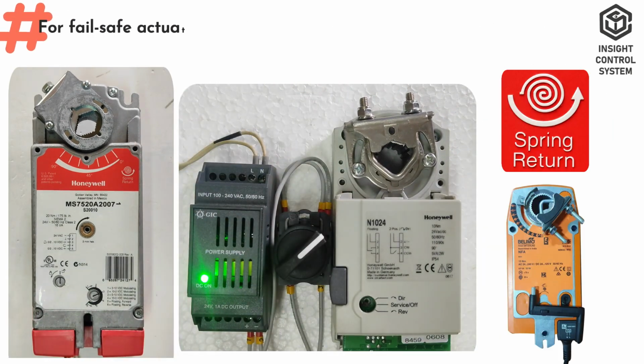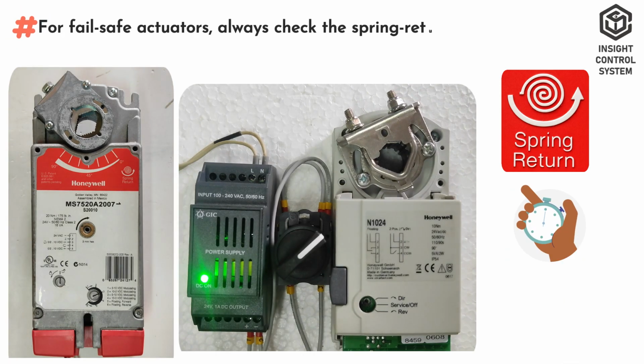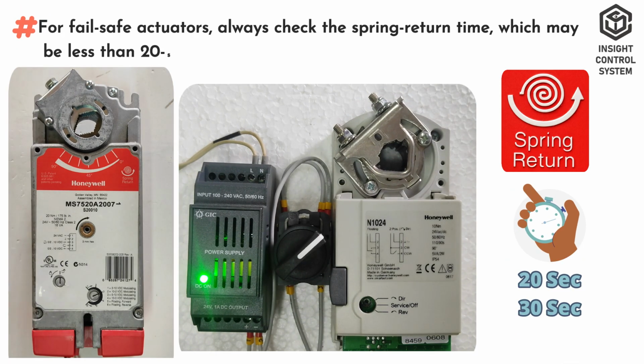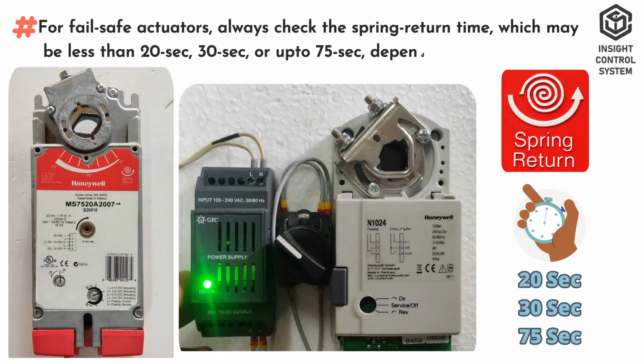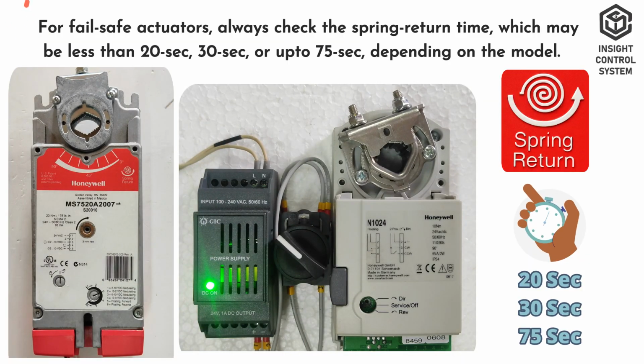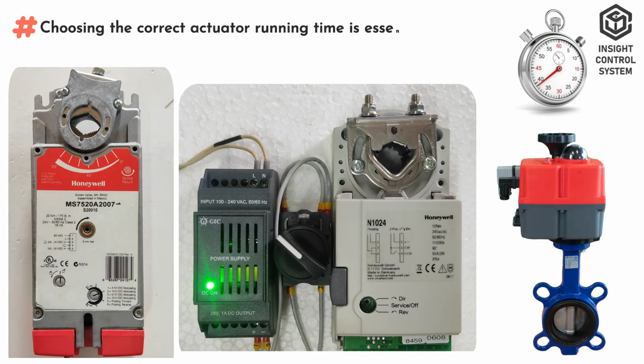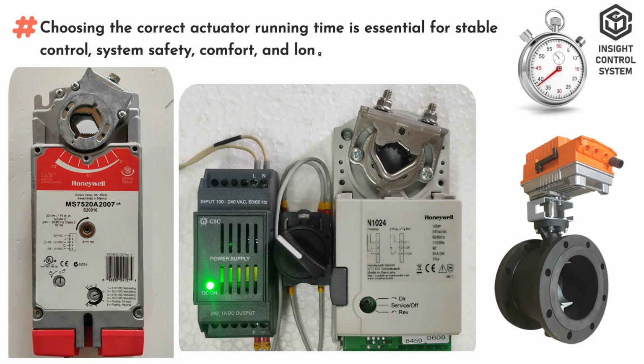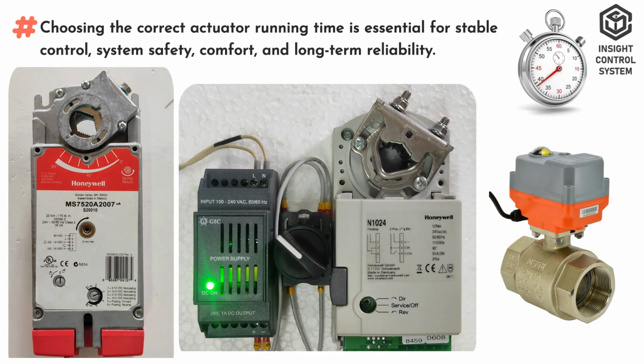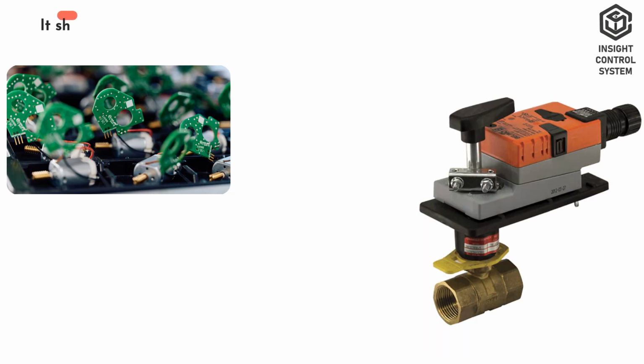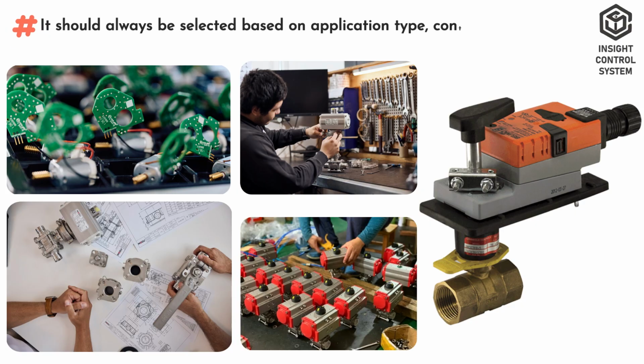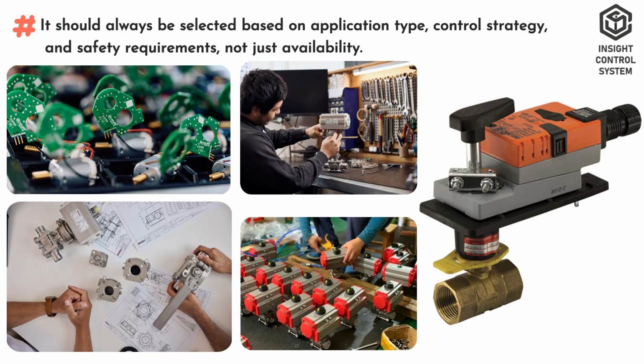For fail-safe actuators, always check the spring return time, which may be less than 20 seconds, 30 seconds, or up to 75 seconds, depending on the model. Choosing the correct actuator running time is essential for stable control, system safety, comfort, and long-term reliability. It should always be selected based on application type, control strategy, and safety requirements, not just availability.